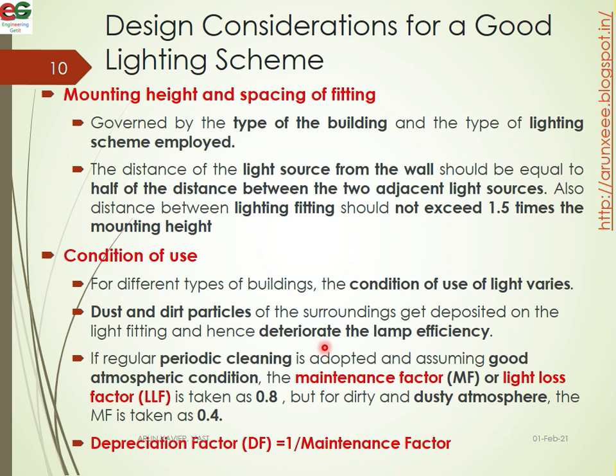Depreciation factor is equal to 1 divided by the maintenance factor, that is, the reciprocal of the maintenance factor. These are important terms in lighting design considerations for a good lighting scheme.